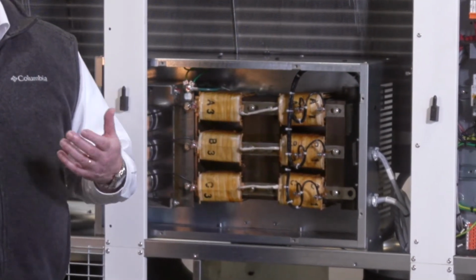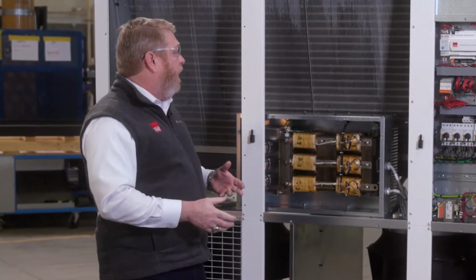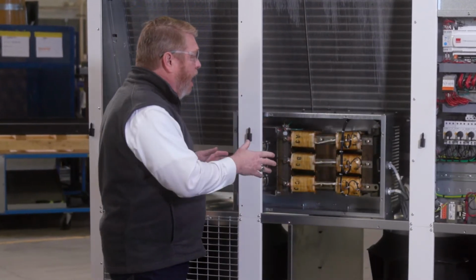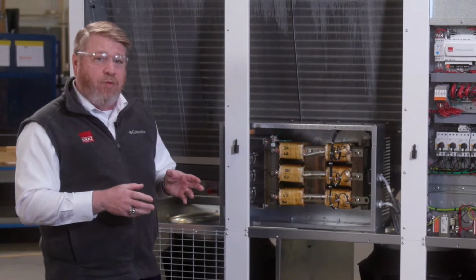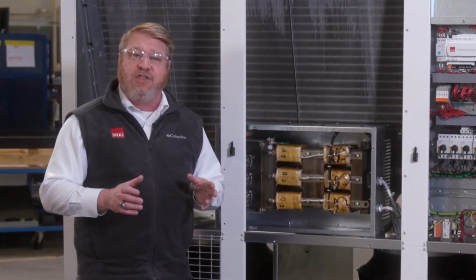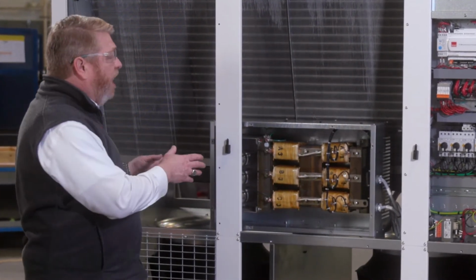So much so that we're talking about things like power increases, heat increases due to I²R losses, and even potentially losing some motor windings inside the motors. Now, what we've done is to provide for harmonic mitigation in accordance with the IEEE 519 standard, we've added, in this case, a passive filter that maintains the total harmonic distortion within acceptable ranges.